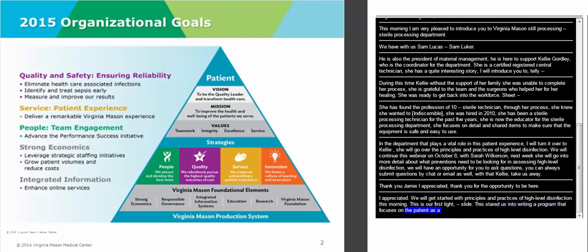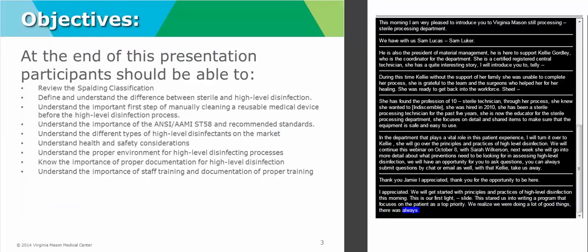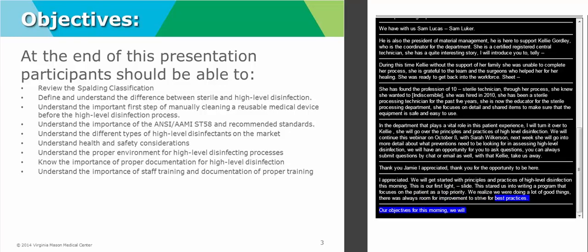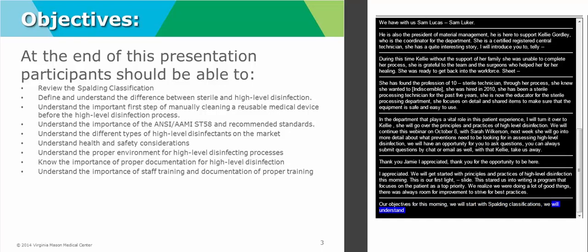We realized we were doing a lot of good things, but there's always room for improvement to strive for best practice. So our objectives this morning for this discussion: first we'll start with reviewing the Spaulding Classification. We're going to define and understand the difference between what is sterile and what is high-level disinfection.